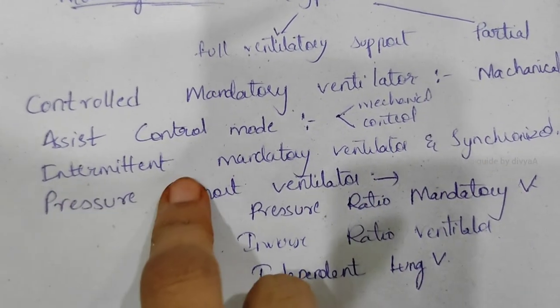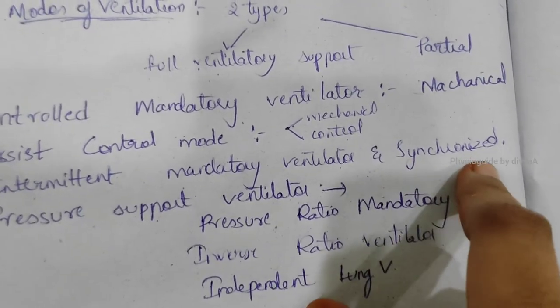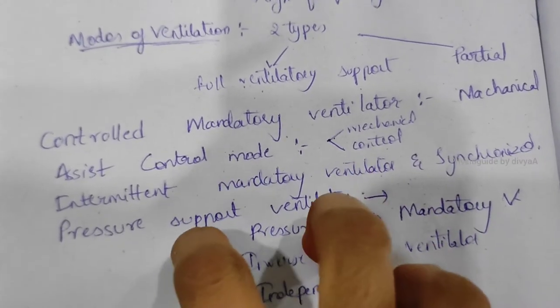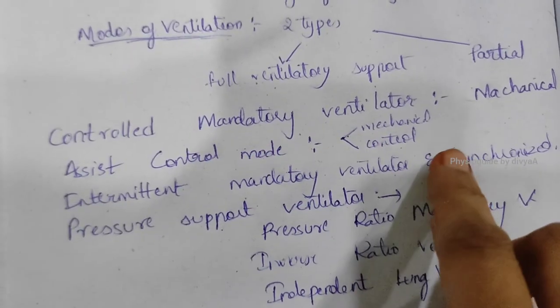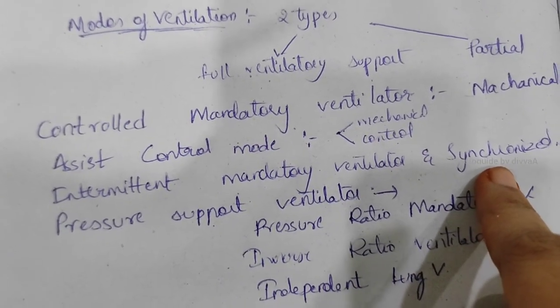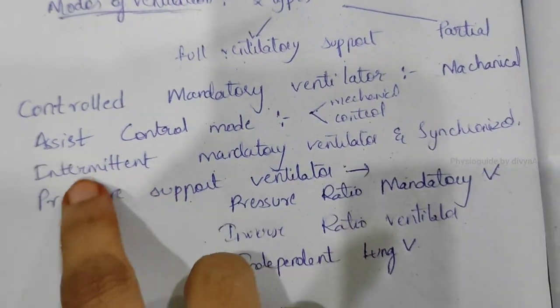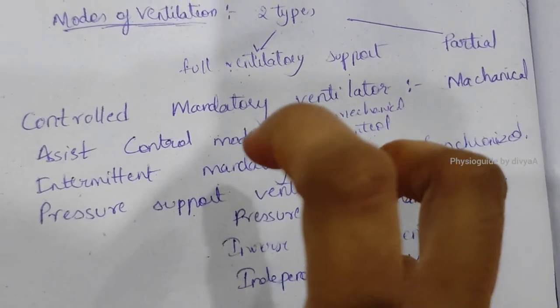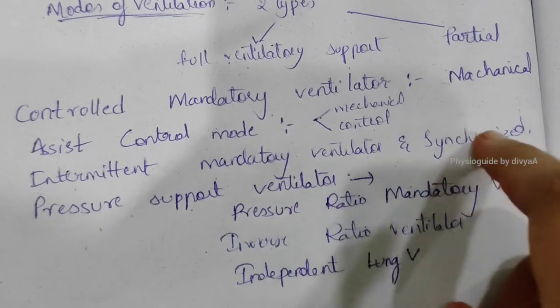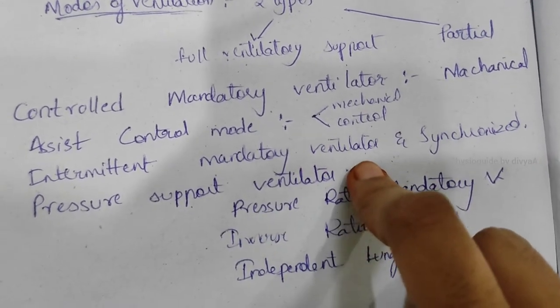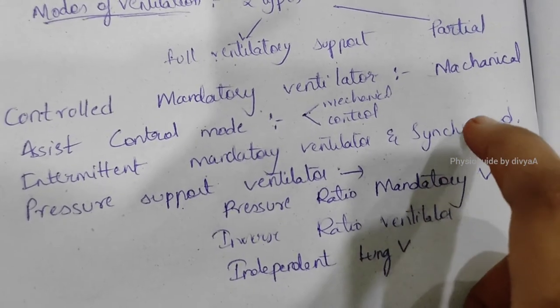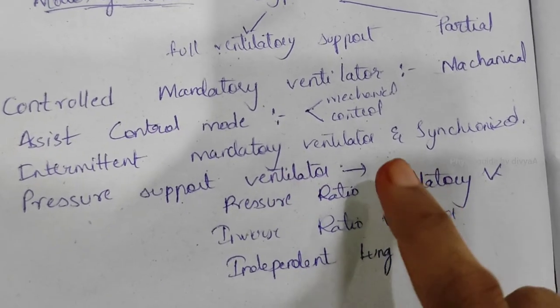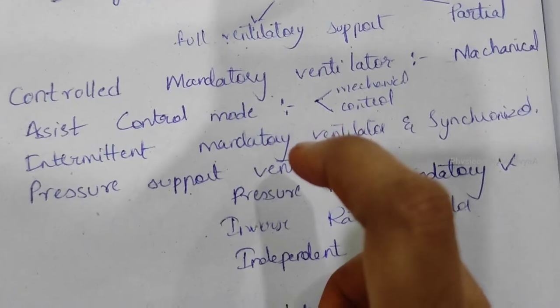Intermittent mandatory ventilation (IMV) and synchronized IMV (SIMV): the patient is free to breathe spontaneously between set mandatory ventilator breaths. In SIMV, the machine synchronizes with the patient's spontaneous effort and calculates the required breath delivery accordingly.